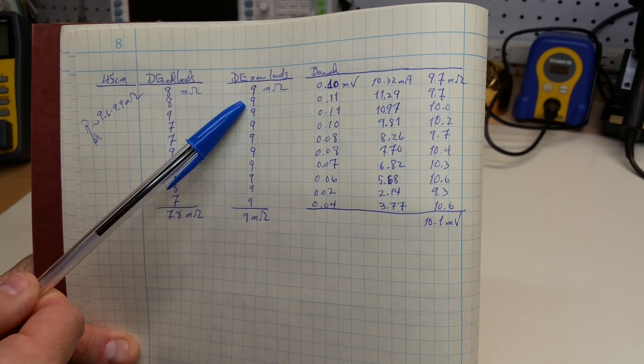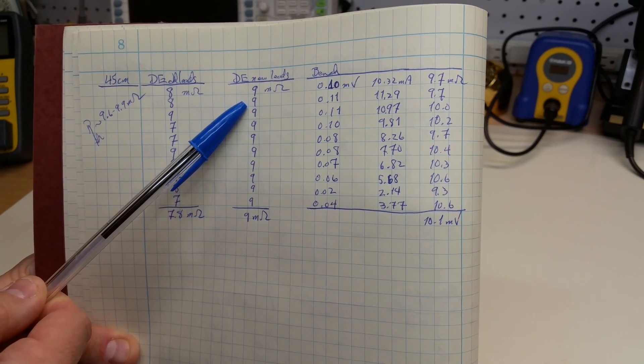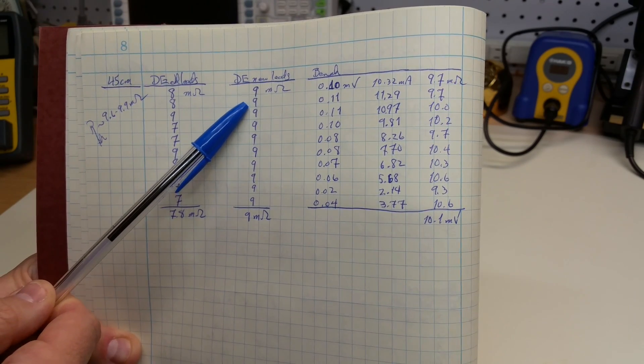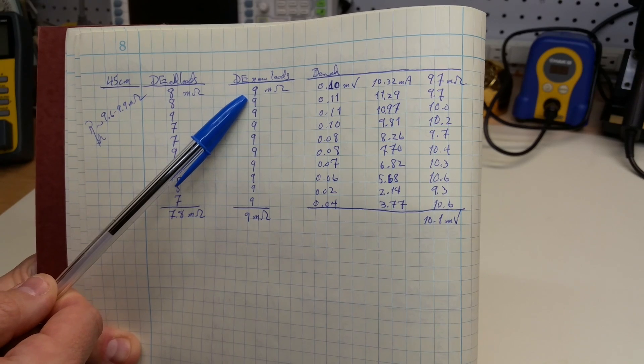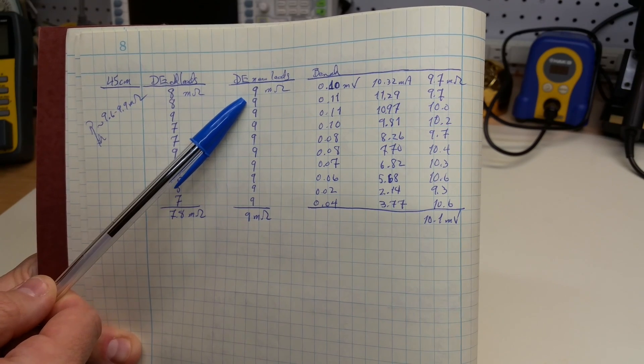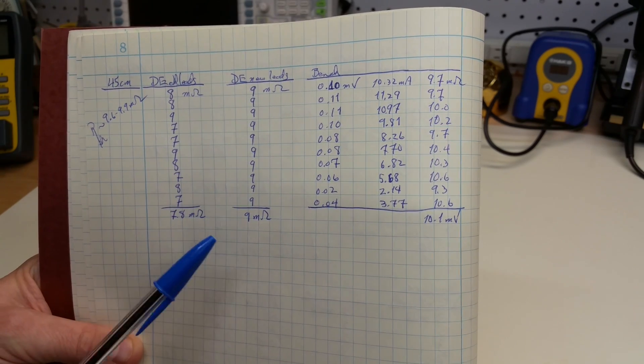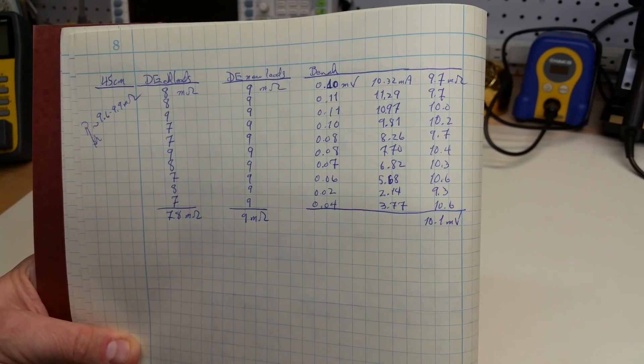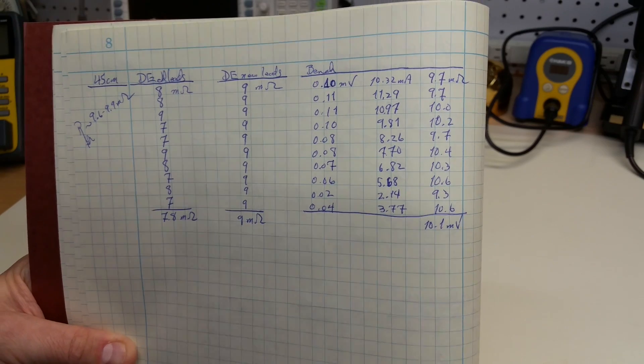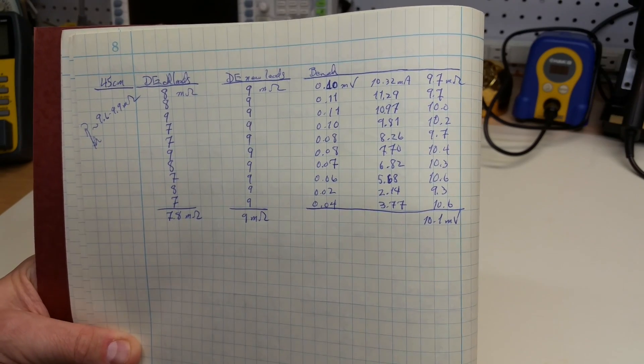When I measure with the Kelvin clamps, the measurements are extremely repeatable. They're all 9's, giving, of course, the 9 milliohms average measurement.